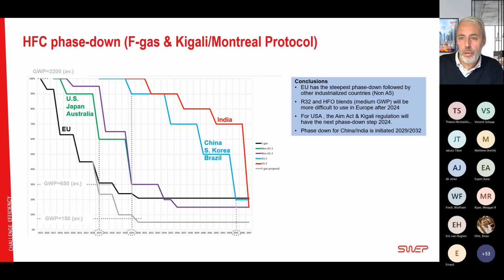So some conclusions from this graph are that the EU has the steepest phase down, followed by the other industrialized countries defined as non-A5. If we define 100% as an average GWP of 2,200, we can see that around 2024, we have an average GWP of 650. So this tells us that on average, R32 and other HFO blends, that is medium GWP, will be more difficult to use in Europe after 2024. And in the USA, yes, the AIM Act will have the next phase down in 2024, and the phase down in China and India is initiated in 2029 and 2032.